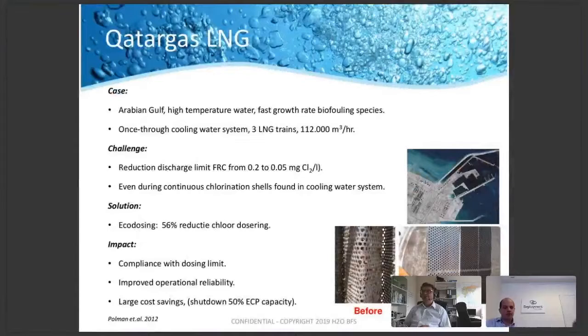An oil and gas installation at Qatargas LNG in Ras Laffan, Qatar. Qatargas used hypochlorite 12 months a year, continuous dosing. They were challenged by the Ministry of Environment in Qatar to reduce the amount of chlorine in their cooling water system. The discharge limit went from 0.2 to 0.05 milligrams per liter, which was a big challenge for Qatargas because even with the discharge of 0.2 milligrams per liter, they still found shells in their system, which meant the dosing was not efficient enough. We changed the dosing regime.